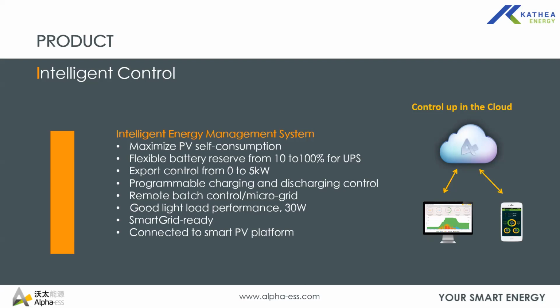So the system, as I've said, the battery has a 90% depth of discharge. So you can drain it from 10 up to 100% on UPS, and it can export PV power up to the rating of the inverter. It's programmable. If you are to feed back to the grid, you can set how much maximum feed-in you would like to push to the grid. It can feed back up to the rating of the inverter, that is 5 kilowatt. It has programmable charging and discharge control, which is a remote function through your app on your phone or through the website on your computer.